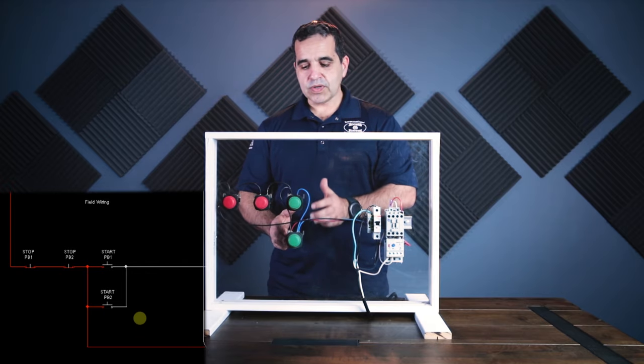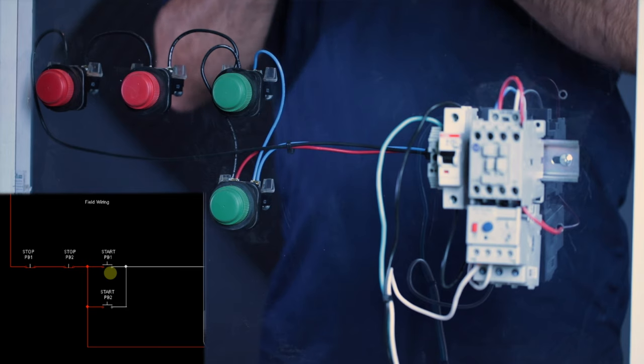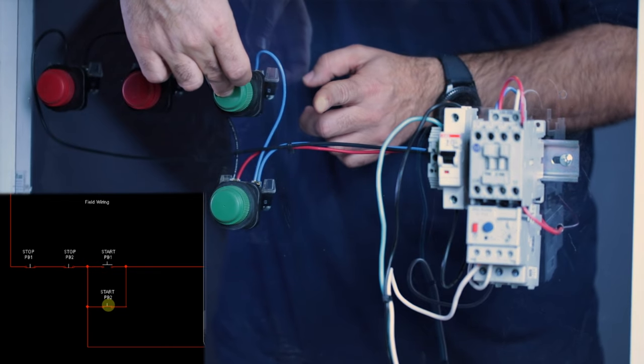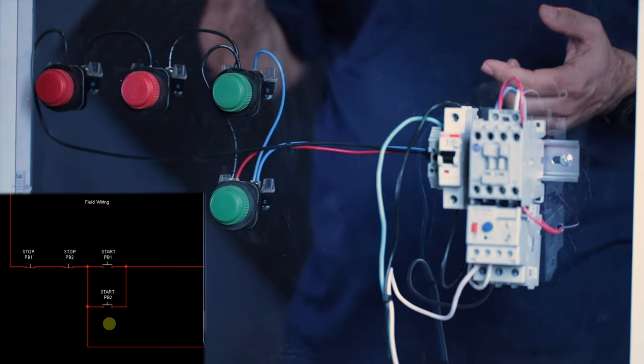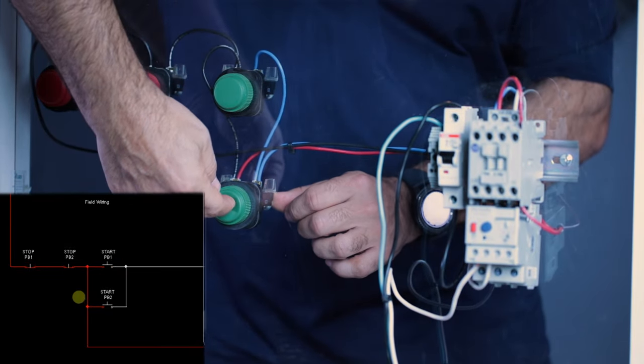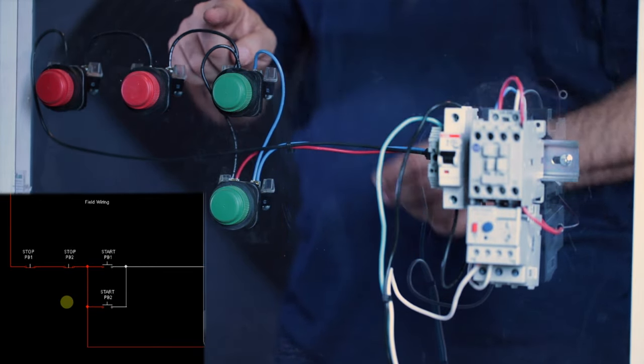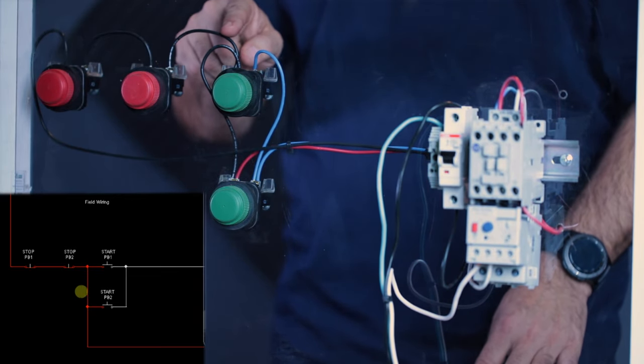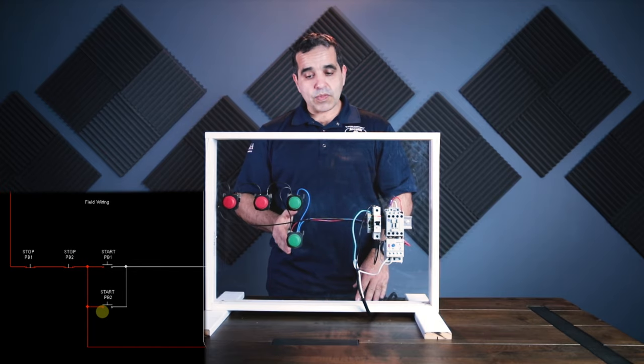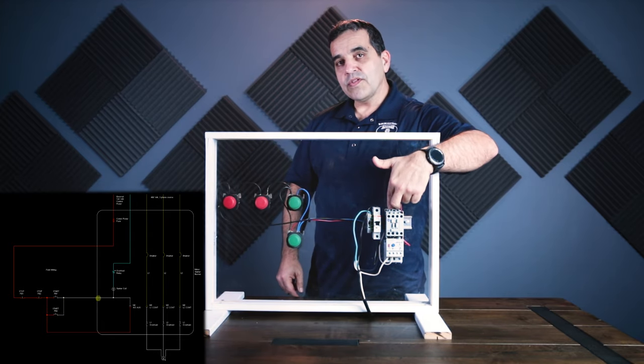That means it can be one start button or the other start button — one or the other will start this motor starter. So these start buttons are normally open, meaning both of these switches are open; the contacts are not connected until somebody pushes the button. When I push the button, our starter is going to start because I closed the contact. When I let go, the contact opens back up and our starter is still on — we'll get to that holding contact in a minute. So either one of these start buttons will start our contactor. We go through our stop buttons, feed one side of each start button — they're in parallel with one another.